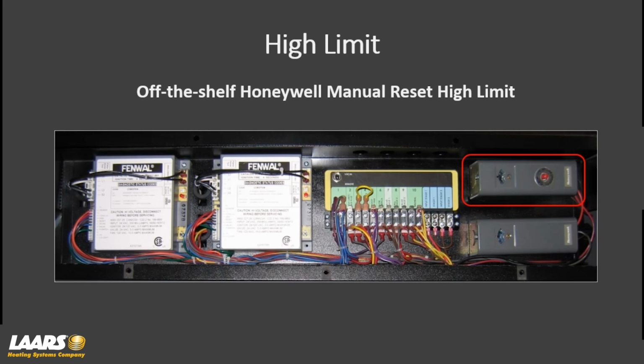Depending if it's a hydronic version or a volume water heating, volume water heating typically is defaulted at 200 degrees. Hydronic would be defaulted at 210. Keep in mind, these are high limits. These are a safety device. Don't drop them down lower.